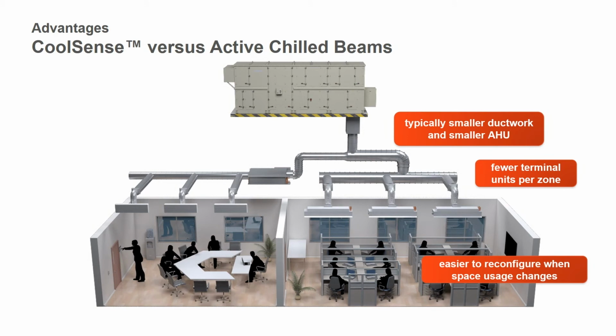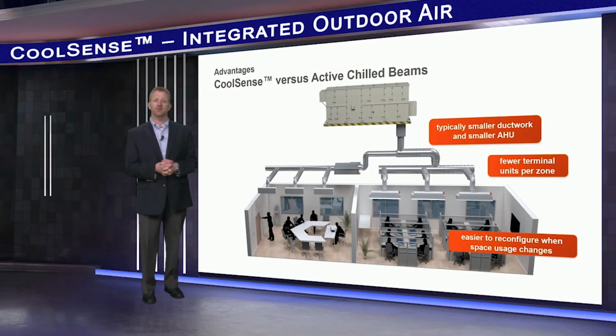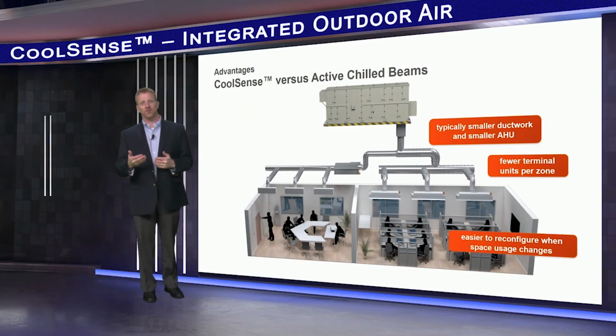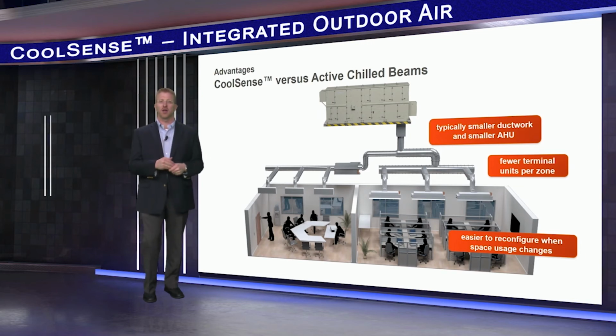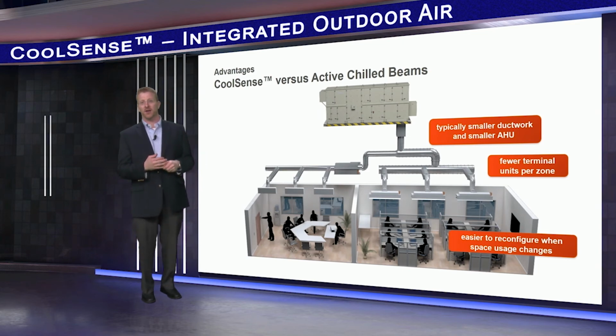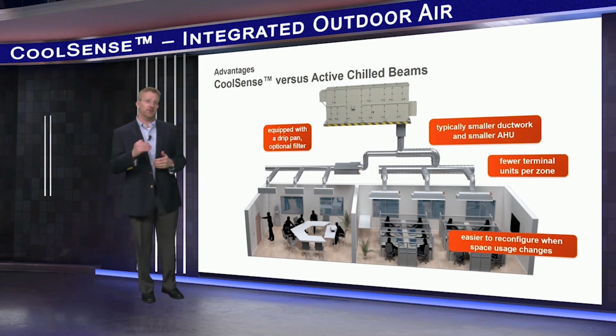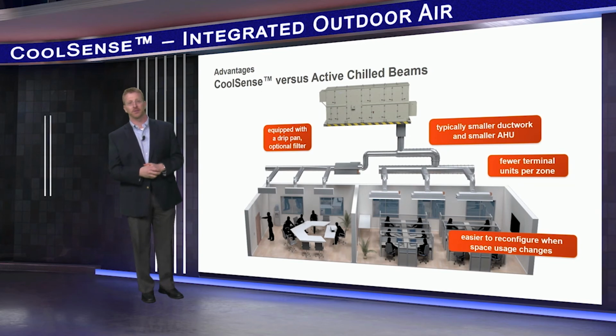Next, CoolSense is more easily reconfigured if the use of the space or occupancy changes. Reconfiguring a zone often requires moving only the downstream flex duct and supply air diffusers. The terminal units and water piping often do not need to be moved, whereas active chill beams are also your diffusers, so the beams themselves often need to be moved, which also means reconfiguring and reconnecting water piping and primary air ductwork. Since neither the CoolSense system nor chill beams have drain pans, there is no need for movement of any condensate lines. That said, CoolSense does have a drip pan to catch any unintended condensate, whereas most models of chill beams do not. So any unintended condensate might drip into the occupied space.